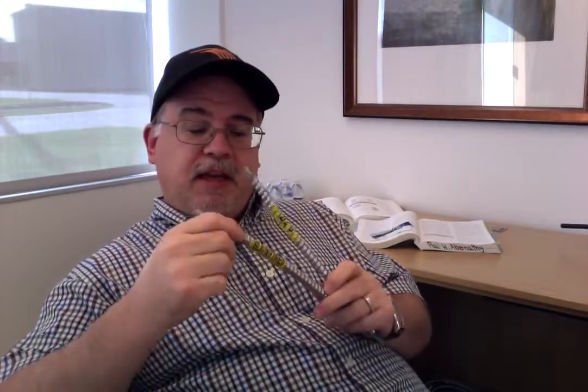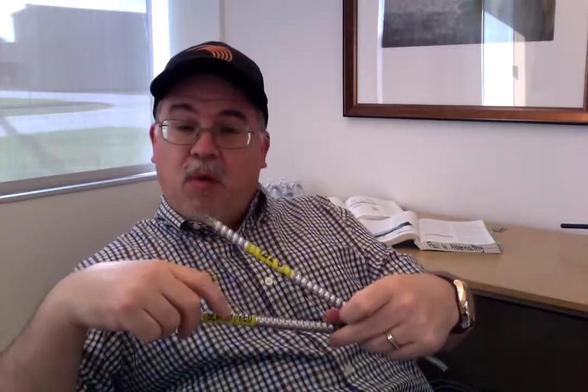But another thing you get on these markings, which again you have every 24 inches, so if one comes off, no big deal. There's plenty to look at for the markings. This one says that it's a 12-3 with a ground, so you know in here it's going to be a what? It also says here a black, a white, and a red. So I know that there's a black, a white, and a red in here. That's the 12-3. And then we have a ground. This ground happens to be insulated, green.